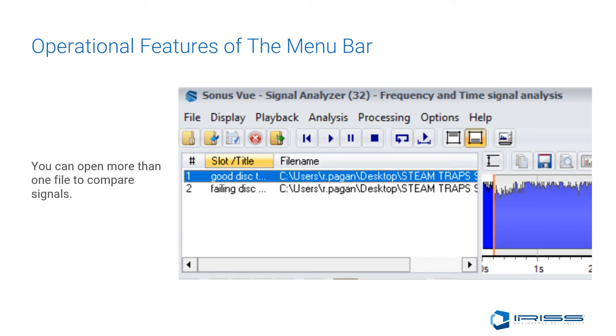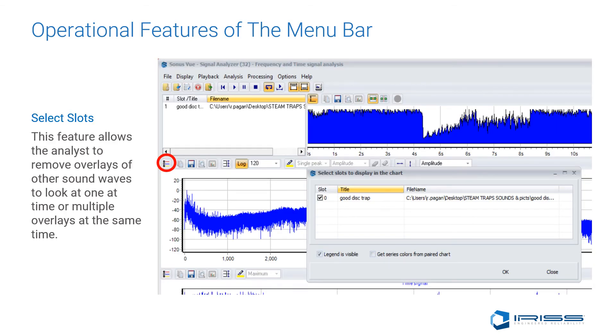You can load up to eight sound waves at a time — any more will make it very difficult to delineate which sound wave is which. This allows you to compare historical information of one asset over time or perform comparison analysis on like equipment to see which one might be an outlier. The Select Slots feature allows the analyst to remove overlays of other sound waves to look at one at a time or multiple overlays at the same time.